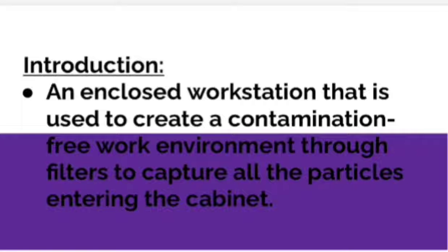Laminar flow cabinets are similar to biosafety cabinets, with the only difference being that in laminar flow cabinets the effluent air is drawn into the face of the user. In a biosafety cabinet, both the sample and user are protected, while in the laminar airflow cabinet, only the sample is protected and not the user.